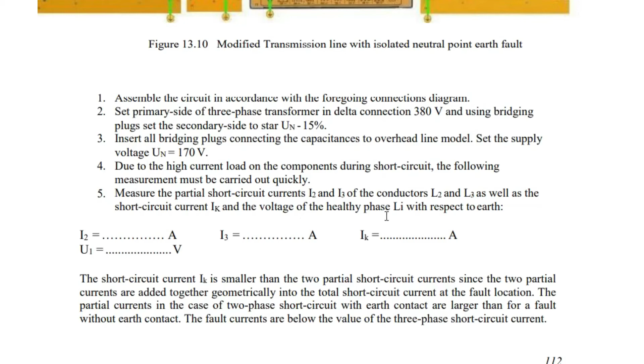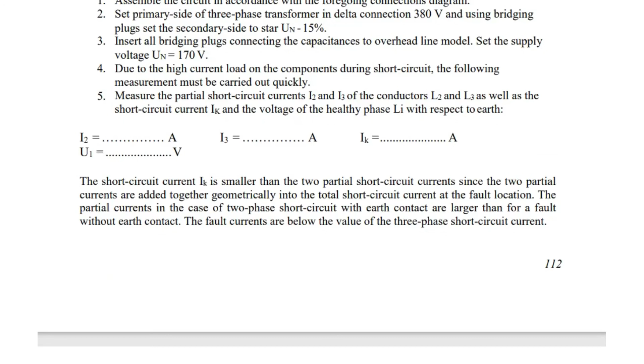Due to high load current on the components during short circuit, the following measurements will be carried out very quickly, and the voltage will not be set to 220 or more than that. We have limited the voltage up to 170, and we will take the readings very quickly. We will measure the second phase current, that is the short circuit current for the second phase, the third phase, and IK. It means this IK is actually the short circuit current, and then the voltage of the healthy phase, that was phase 1, which was healthy because it was not short circuited. Okay students.